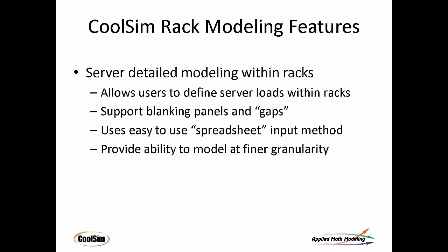And we also support blanking panels and gaps, and I'll show you that. This allows you to get more granularity in the rack row itself, because the first level of detail is I'm going to assume that the average watts per rack is X, because it may be a new design and you don't know what the loads are going to be, or it may be an existing design but you don't know what the loads are. So we have to start somewhere with assumptions.